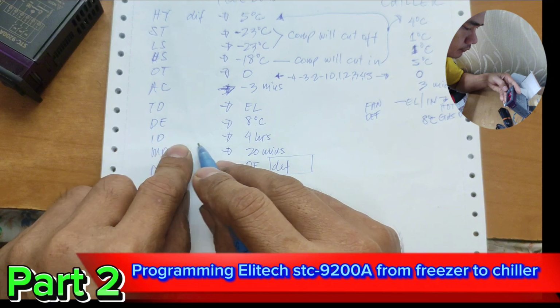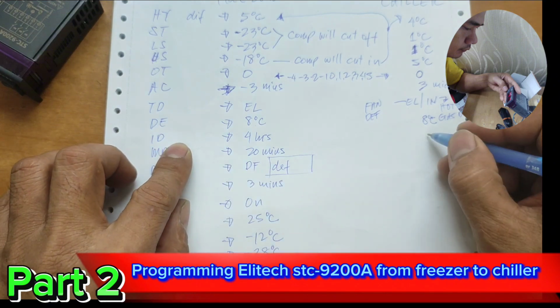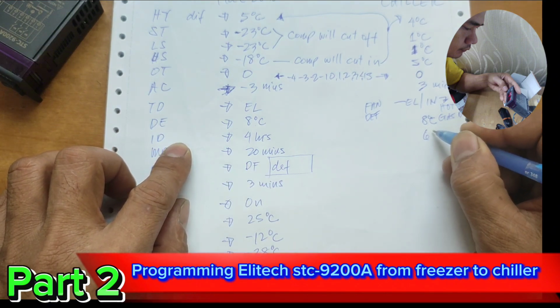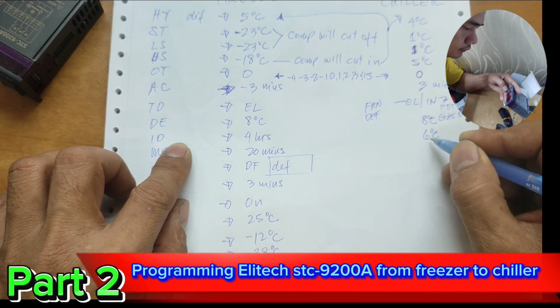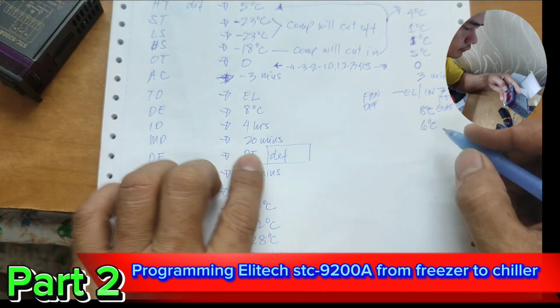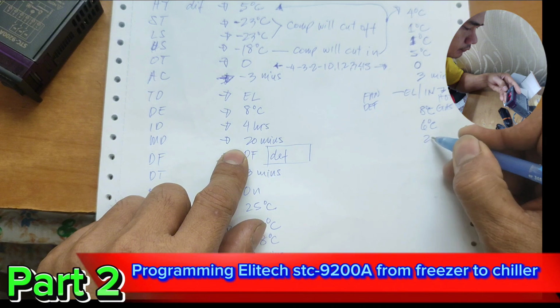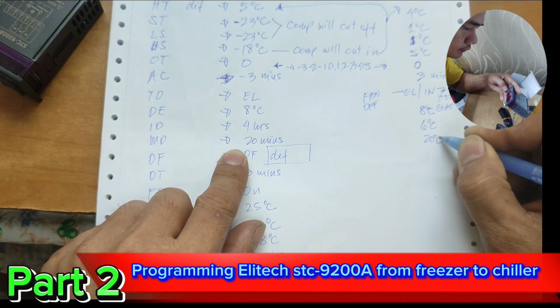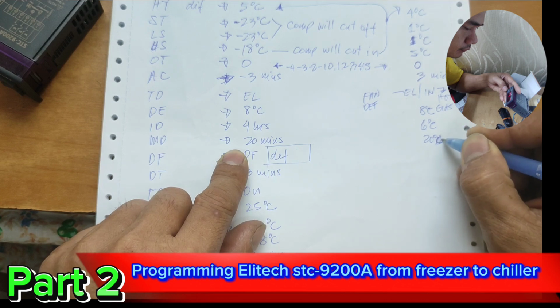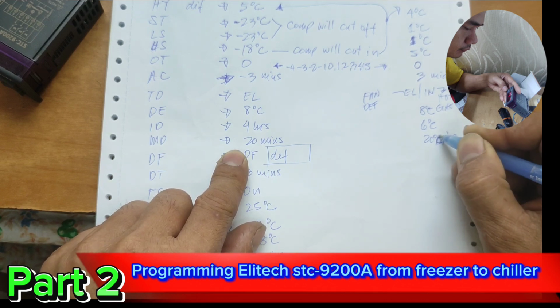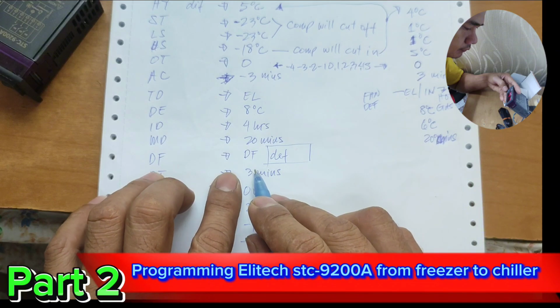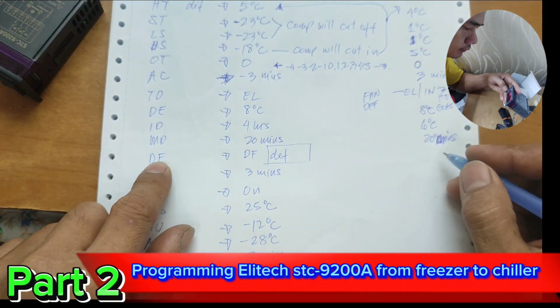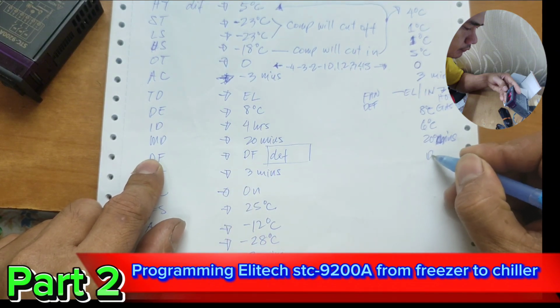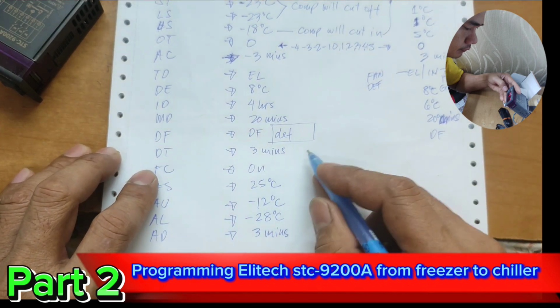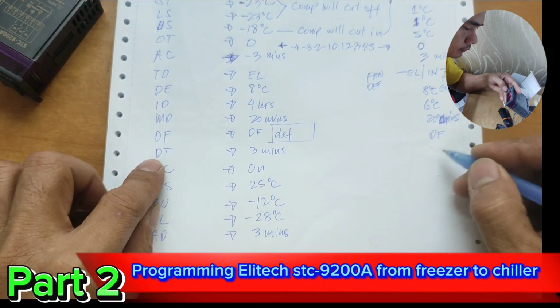For the defrost cycle, choose 6, no problem with the 6, every 6 hours it will defrost. For the MD, you can go 20 here, guys, 20 minutes. And for the DF label, just go for DF again, and same, 3 minutes for the dripping time.